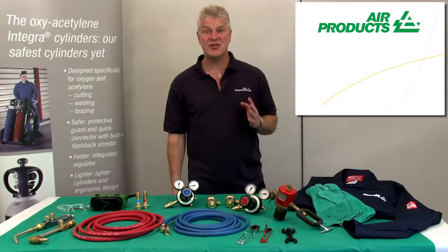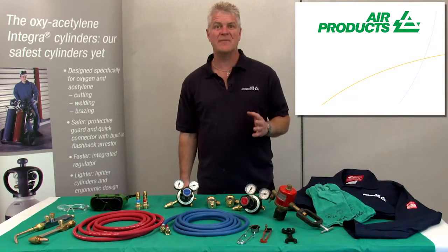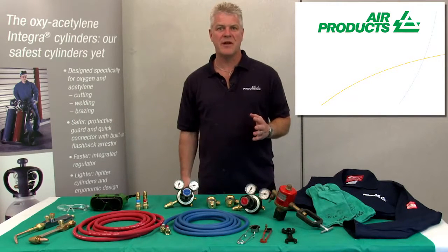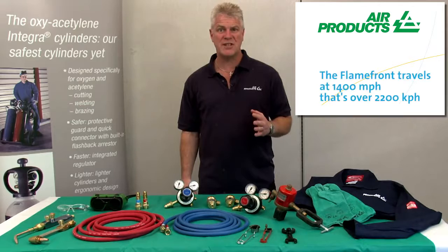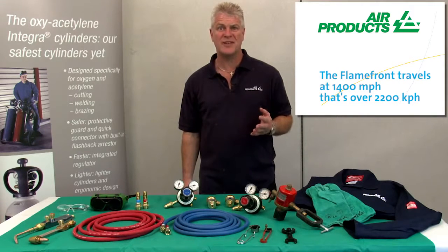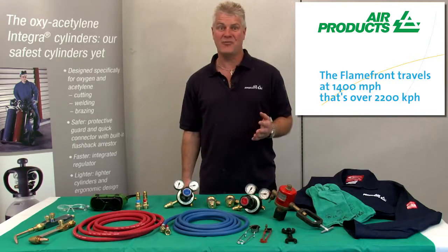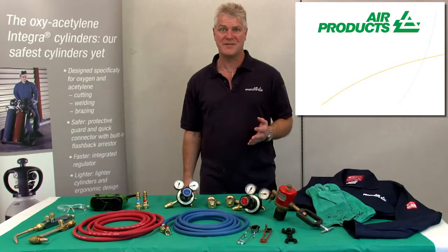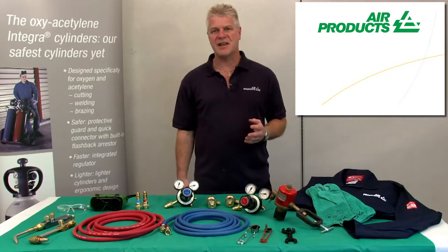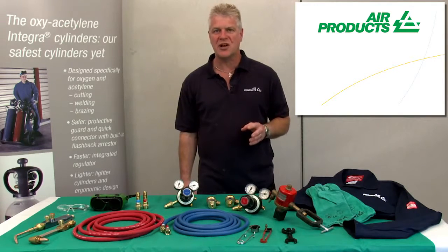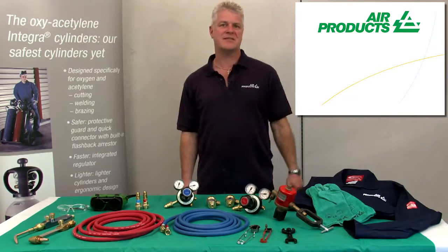A flashback has two components. It creates a flame front and a pressure wave. The flame front moves with a speed of 1400 miles per hour or over 2,200 kilometers per hour, and a non-return valve will not stop it. Flashback arresters in both the oxy-fuel and oxygen lines must protect the regulators and the cylinders.